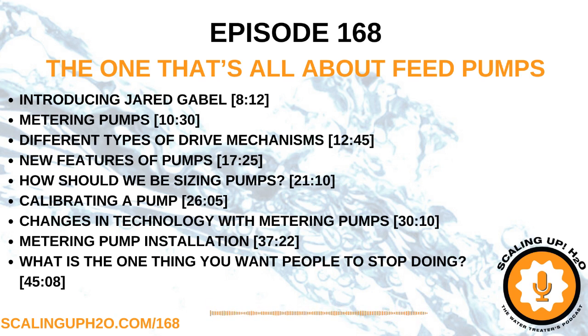Is it safe to say if you're using a gassing chemistry, you really don't need to set the stroke for anything less than 100%? I bet that's really for the pumps that we make at Grundfos. All we're doing is controlling the speed now. We adjust the speed, and we can do that basically independent of the stroke setting, or where the stroke is at in the travel. So I can take a suction stroke in very quickly, and then I can push it out very slowly, to then dial it down through the turndown ratio or get the sweet spot that I need on my feed rate.